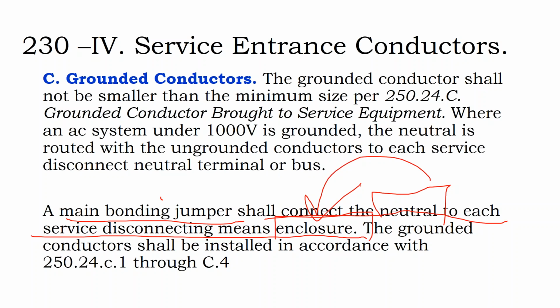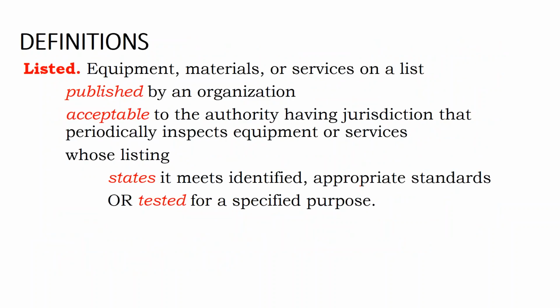And at one point in the system, the neutral is connected to ground as well, and that provides a reference, so that if you're monitoring your neutral wire and you have a reference point to ground, you can compare the voltage in the neutral to ground to determine if there's a ground fault, to enable your ground fault detection systems. But it only occurs at one spot. Now, if you're grounding the neutral and connecting it to ground at multiple spots across your system, then you're eliminating that reference point. Your ground fault detection circuits have a blind spot in them.